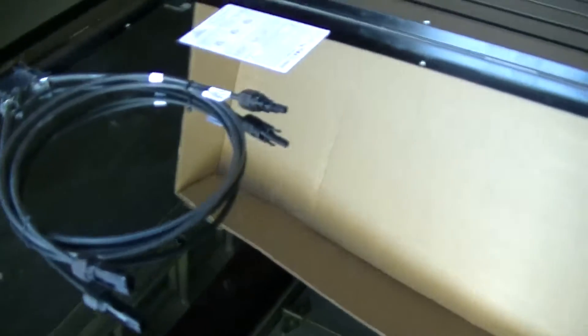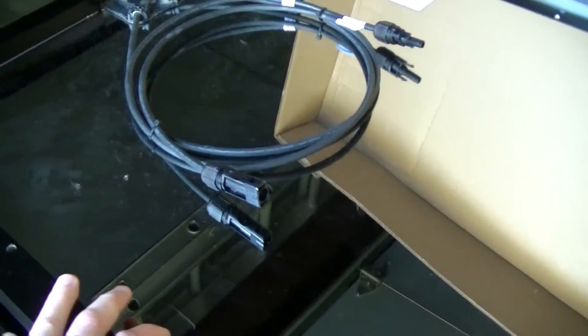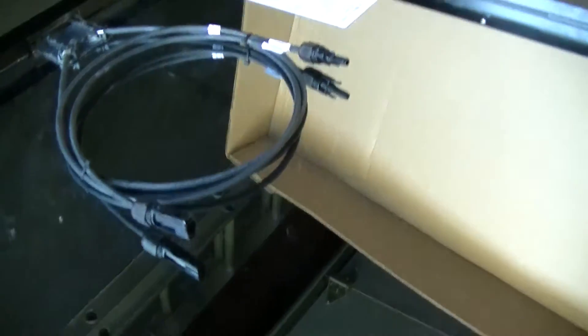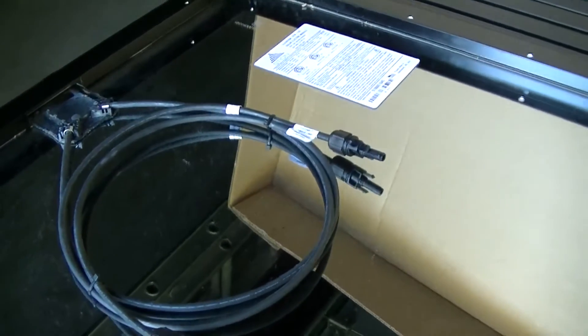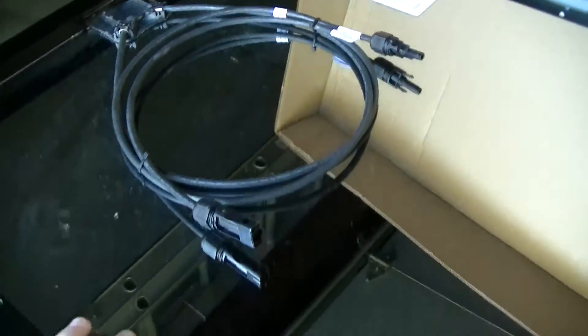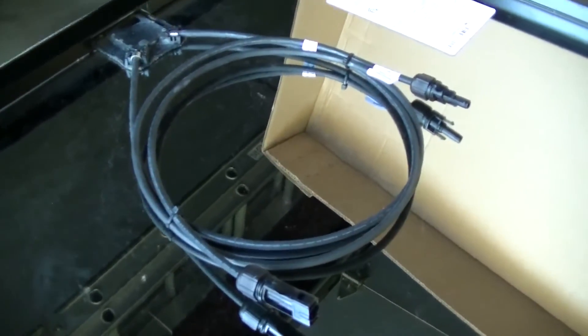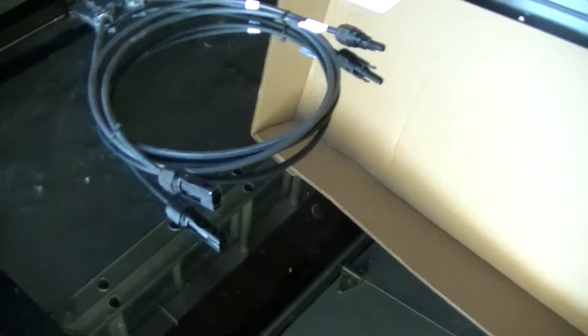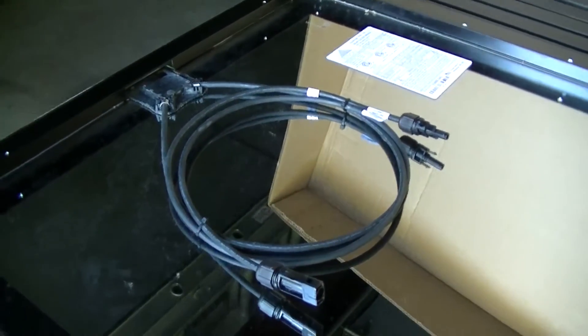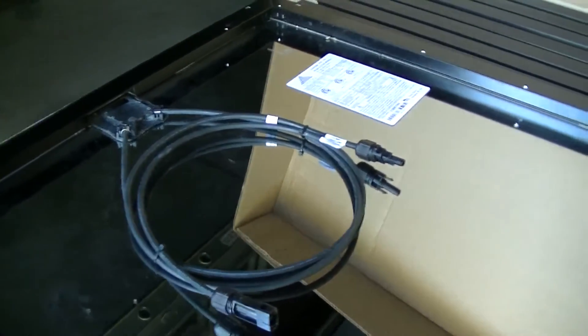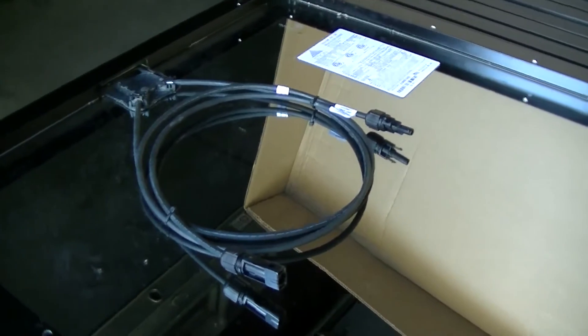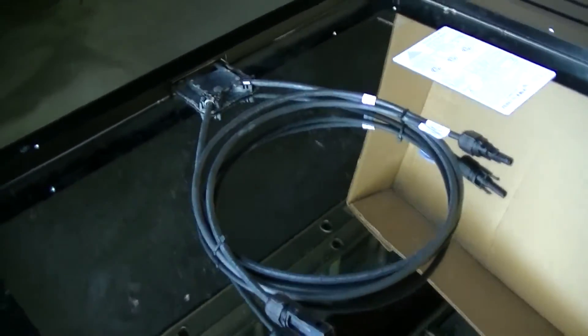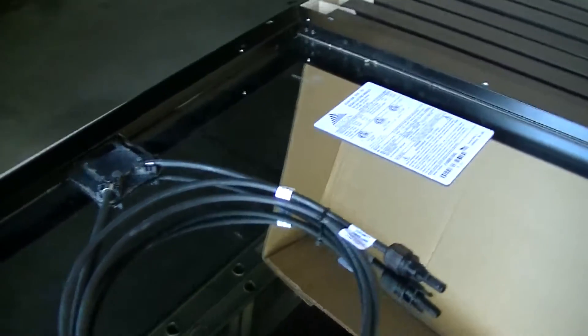So I guess I'll talk about inverters a little bit. So the inverter I think we're going to go with is the Sunny Boy, or the SMA Sunny Boy 3000 TL. That's the transformer-less model, the 3000-watt model. And we mainly are going to go with that because the input voltage is rated at 600 volts, or it's like 150 to 600 volts DC. So that means that if we have 600 volts coming off the roof, there's very little losses in wiring. So you can have small wires like this and it's not going to have much loss.